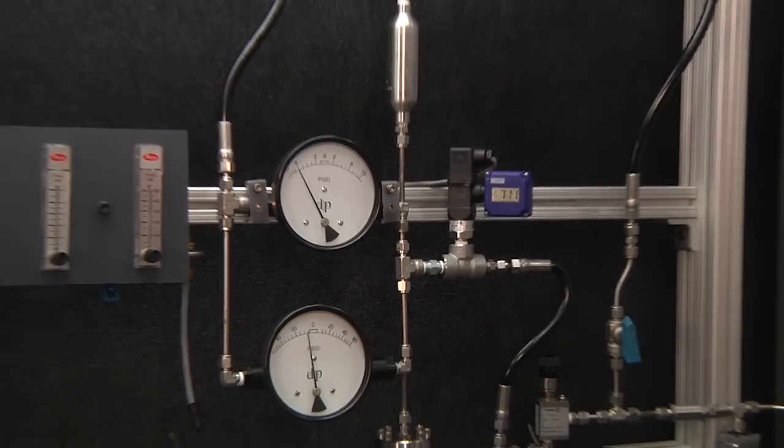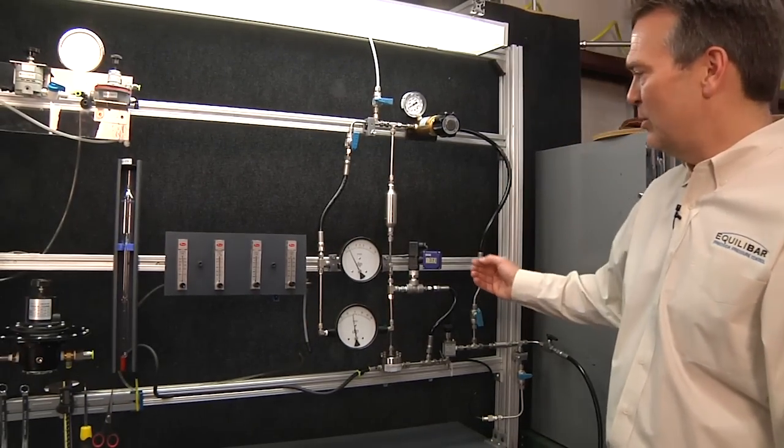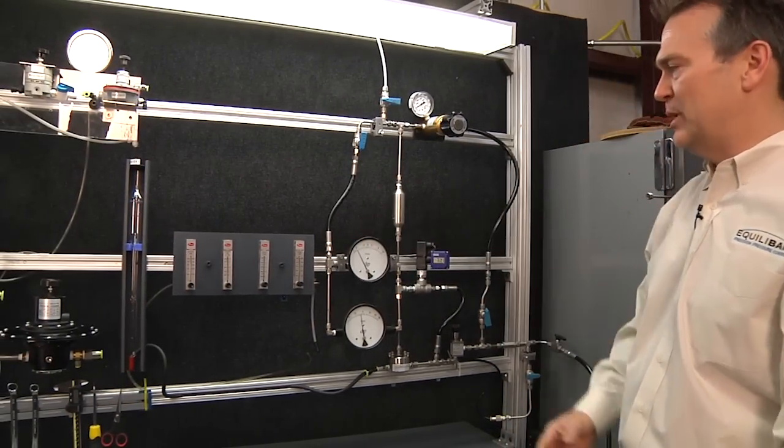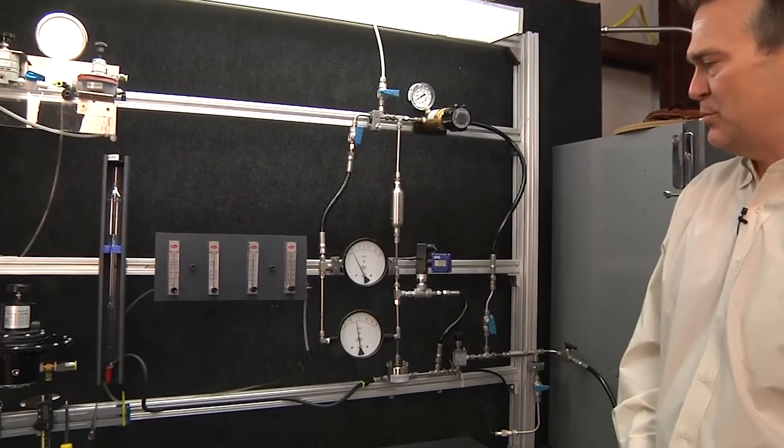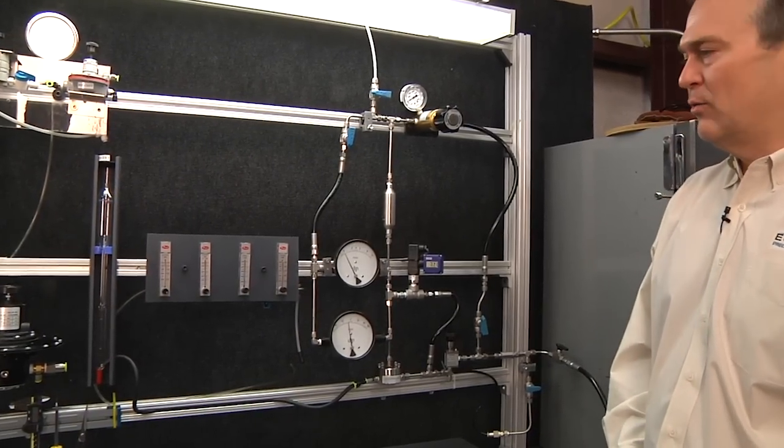If we were to hold this for hours or days, we would see the regulator continuing to hold. It may drop another couple psi but we'll still be holding within about 0.3 percent precision even after we have a hard reactor shut down over hours or days.